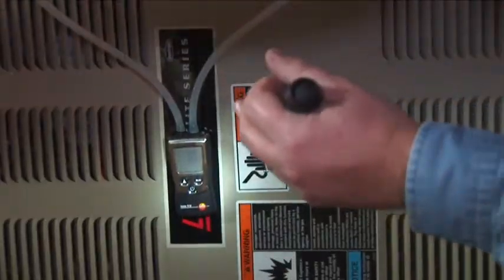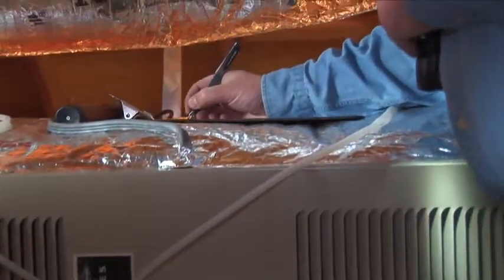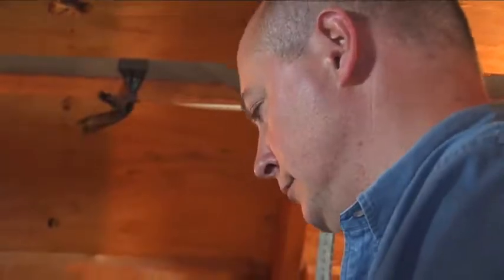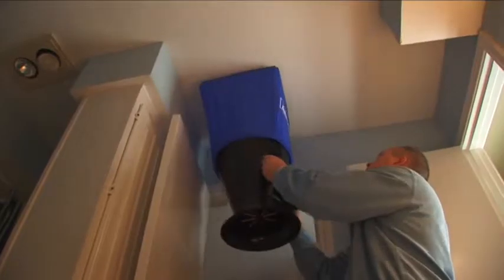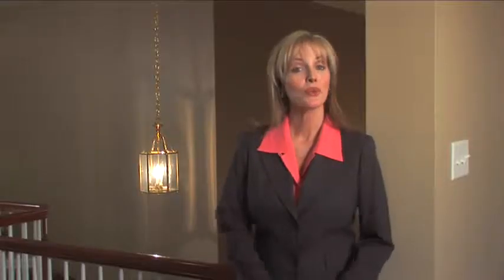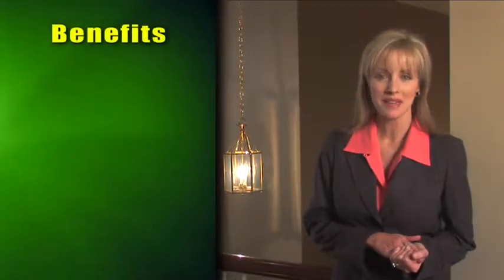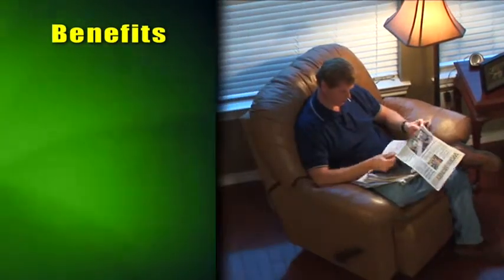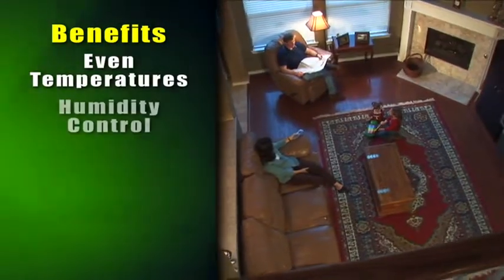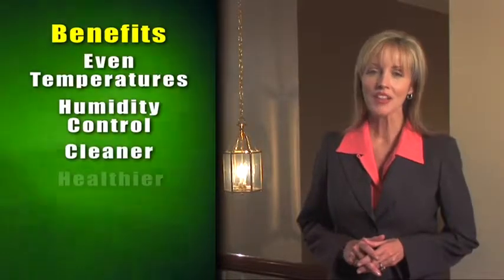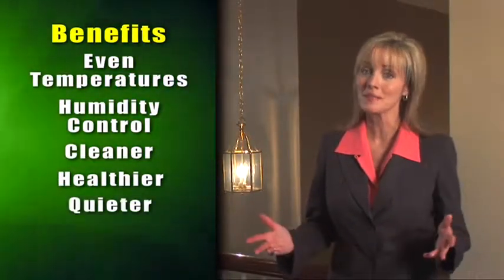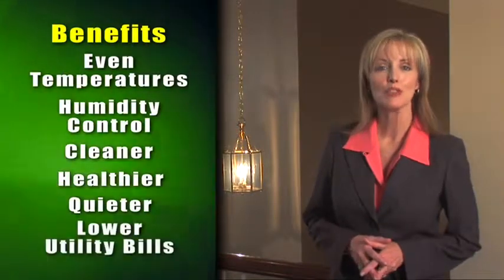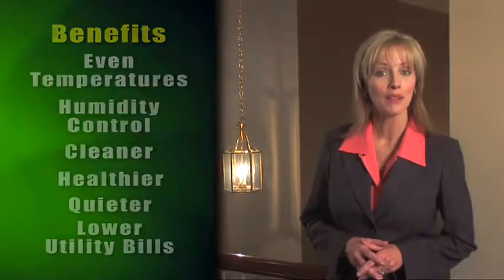A good contractor won't just assume that your new or renovated duct system was done right. They'll offer to test out, checking key factors such as tightness, pressures, airspeed, and airflow to ensure you get what you paid for. Whether you choose to renovate your old duct system or fully replace it, improving your ducts provides many benefits. Most homeowners experience more even temperatures throughout the house, better humidity control, a cleaner, healthier indoor environment, quieter system, and best of all, the investment is usually quickly recovered through lower monthly utility bills.